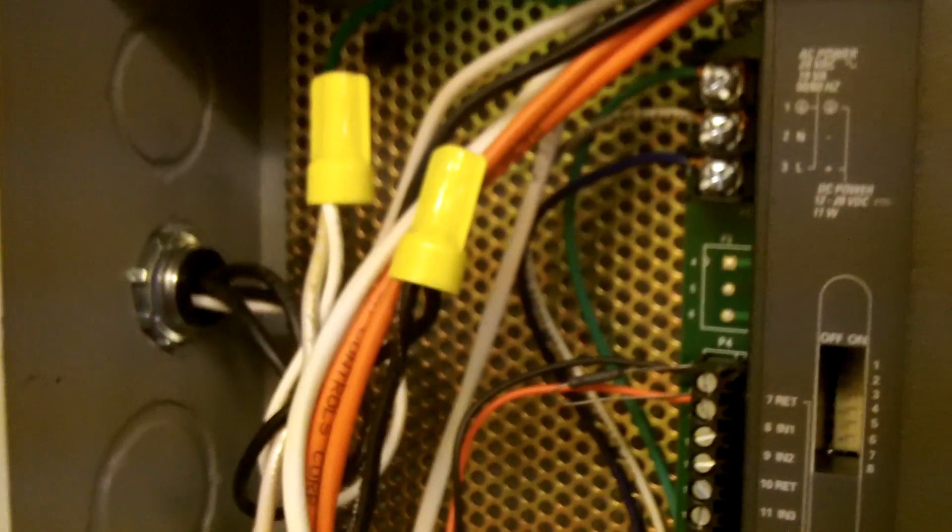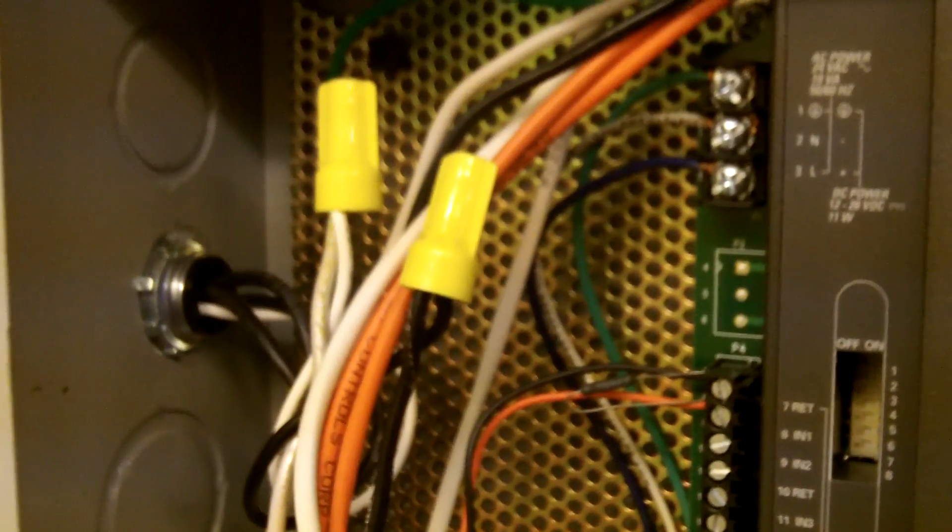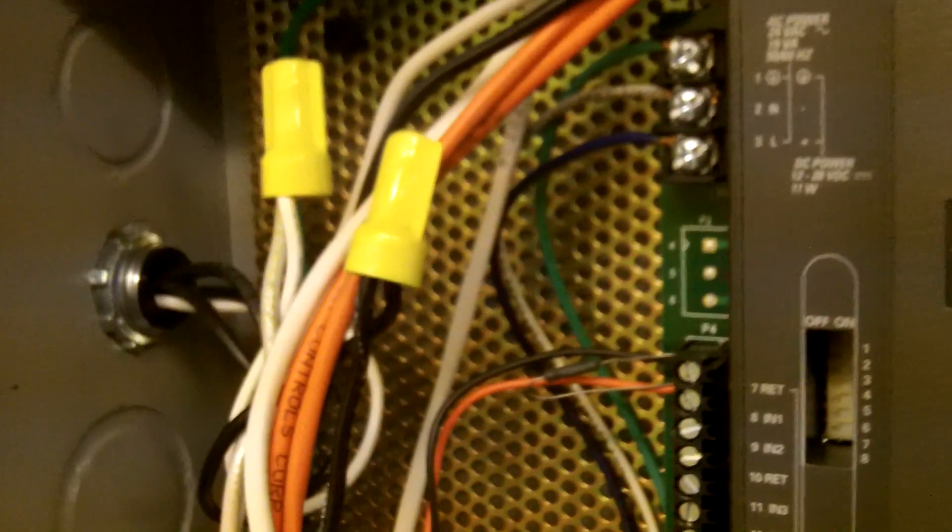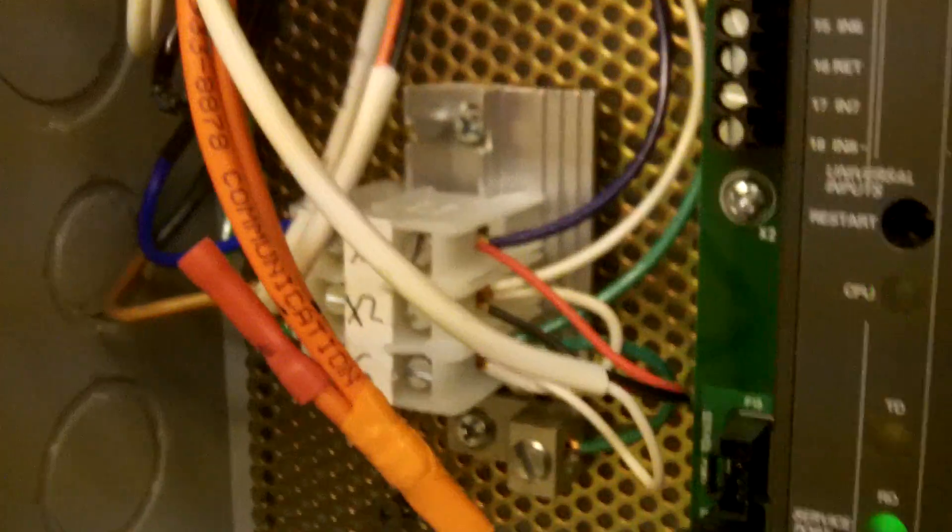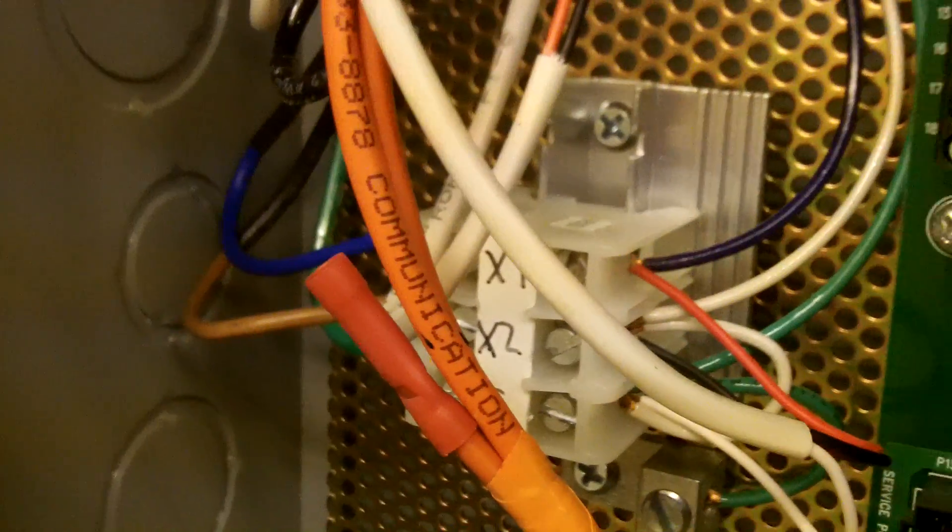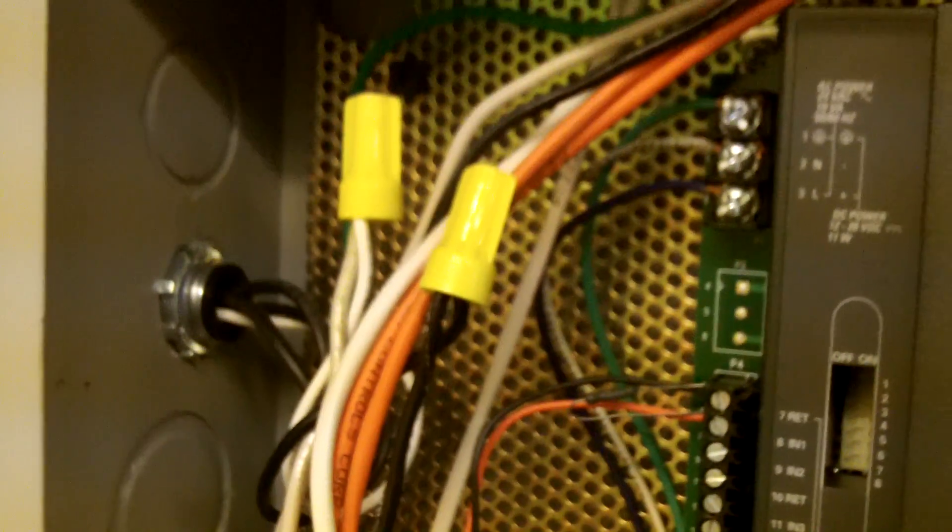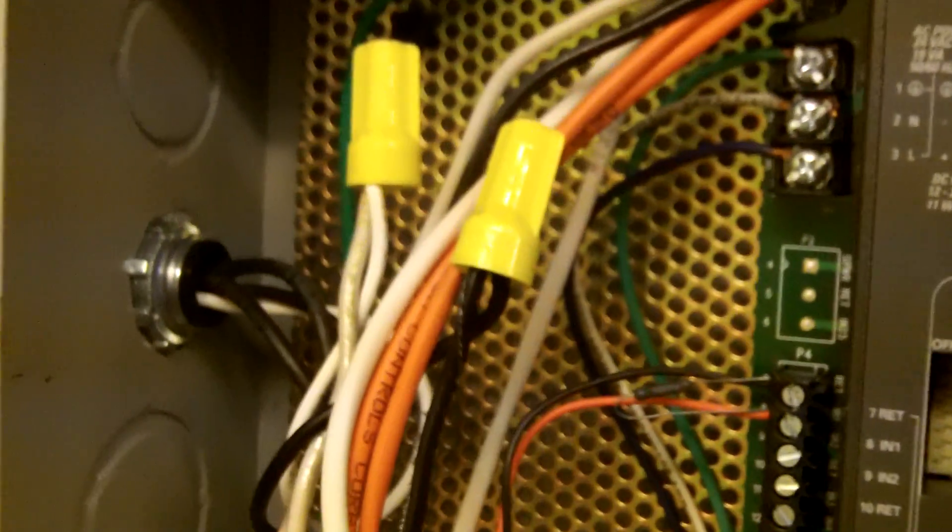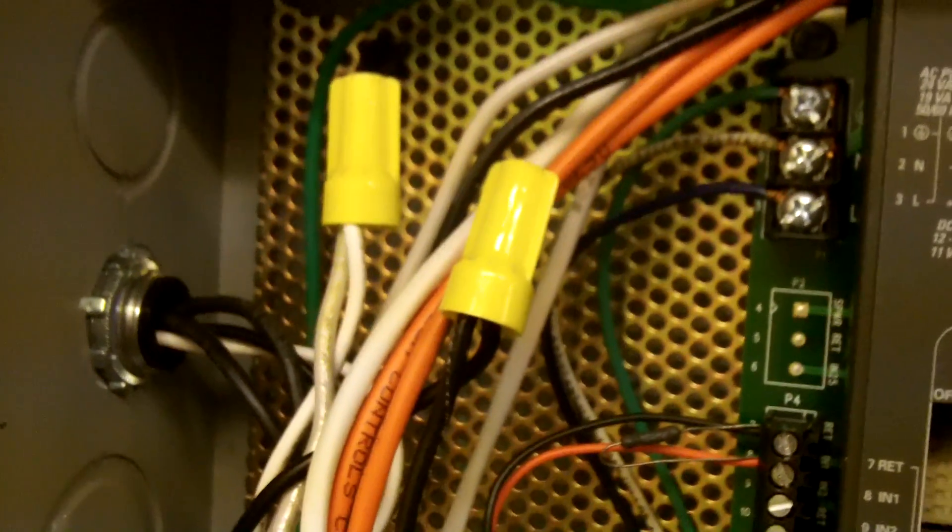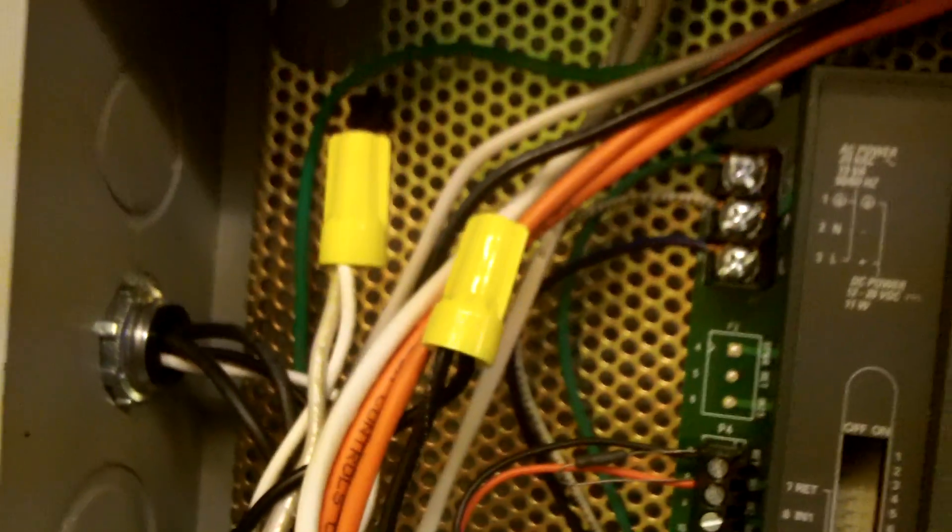All right, in this situation, I'm taking a look at these orange communication cables we see. These are in contact with these power conductors. That's the black and white right there inside this enclosure here.